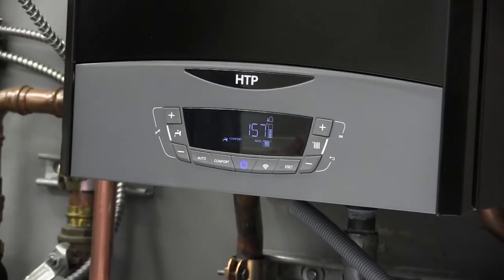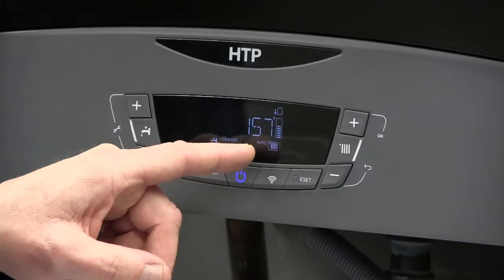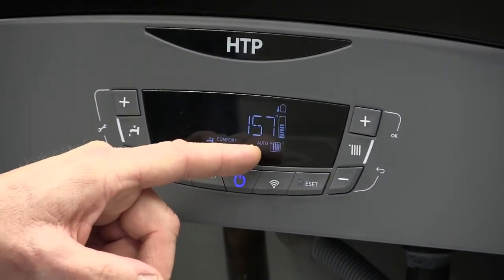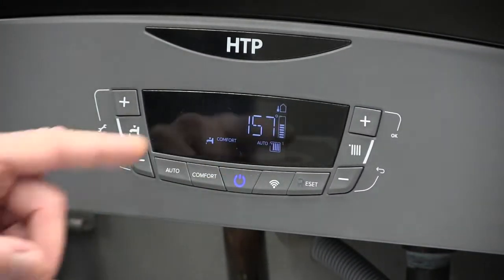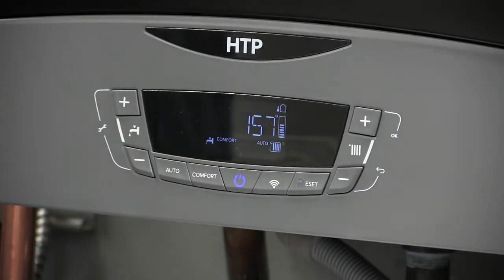But what we always have to make sure is that we look at the control display itself. If you see the auto word displayed, that indicates that the outdoor reset strategy is engaged. If you do not want the outdoor reset strategy engaged, you'll have to hit the auto button again.